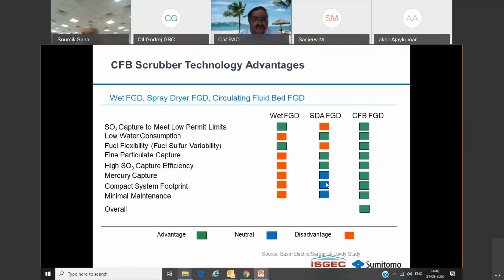Then higher SO3 capture. In semi-dry FGD, SO3 can be captured to a large extent. However, in wet FGD it can be 30 to 40%, depending upon the situation, maybe a maximum of 50% or so. Here in dry FGD, we can go even 90% plus SO3 reduction, which is beneficial for the downstream system from a corrosion perspective. Then mercury capture we can have in semi-dry FGD with activated carbon injection, but in wet FGD this facility is not there. The footprint is compact because far fewer systems are required for semi-dry FGD than for wet FGD, and maintenance is very low because it is very simple. From a corrosion and abrasion perspective it is much lesser than wet FGD.